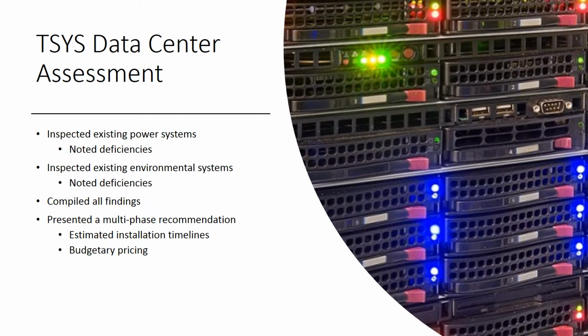An example of a Level 1 assessment deliverable would be very similar to the one provided by K&A for the TSYS data center, minus the PUE calculation. The TSYS data center is located in a brick-and-mortar building located in Tempe, Arizona. The infrastructure consists of one large data room, 2 supporting IDFs, and a call center. For maximum uptime, the data room is supported by redundant UPS systems and protected with an 800 kW diesel-powered generator. The room environment is conditioned using 7 perimeter DX air conditioners and a Stulz humidification system.